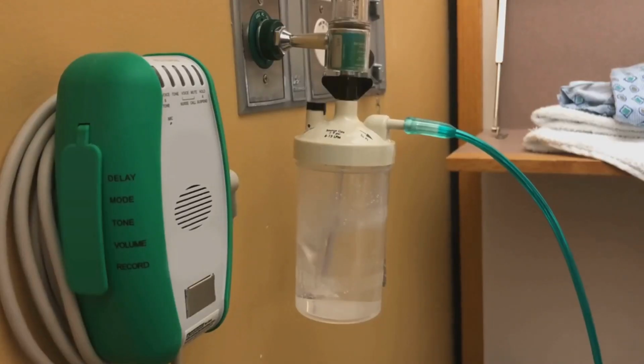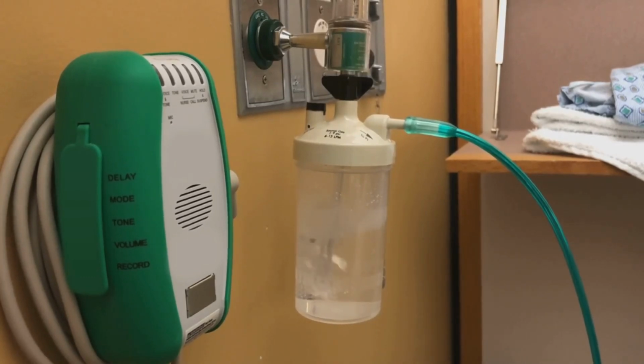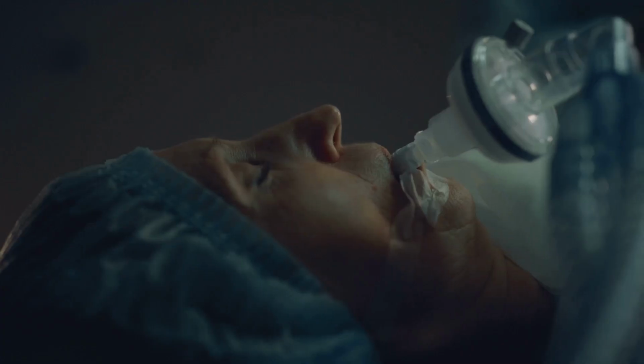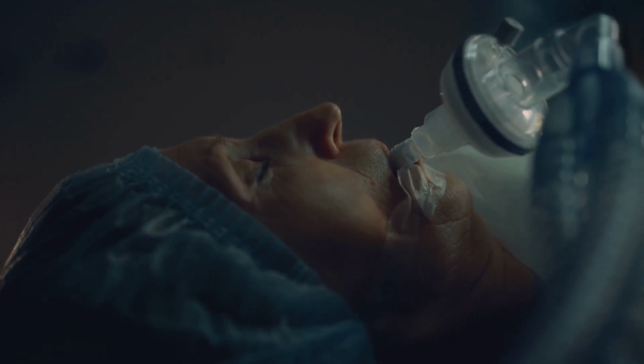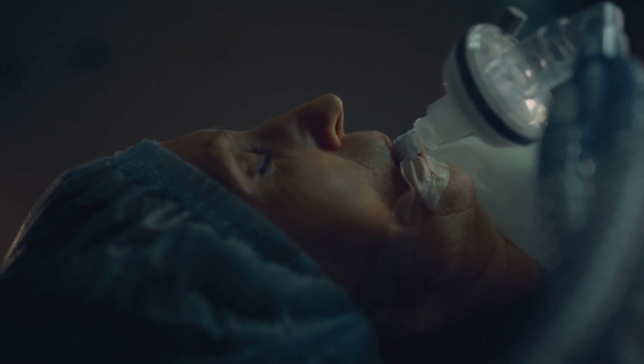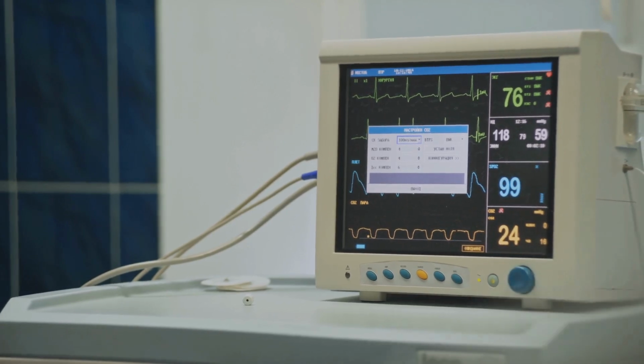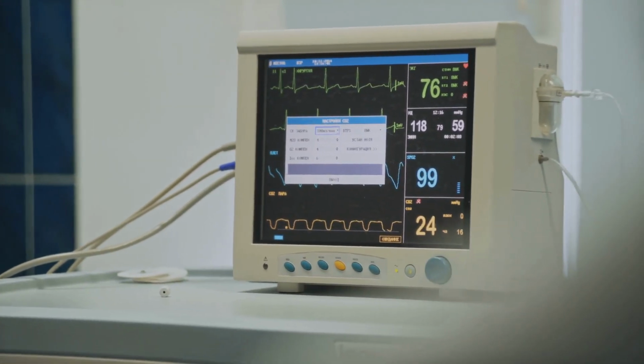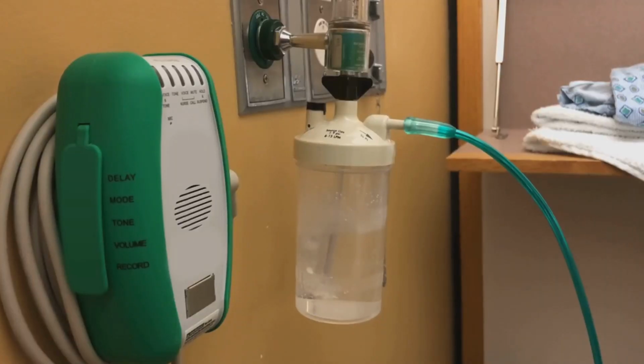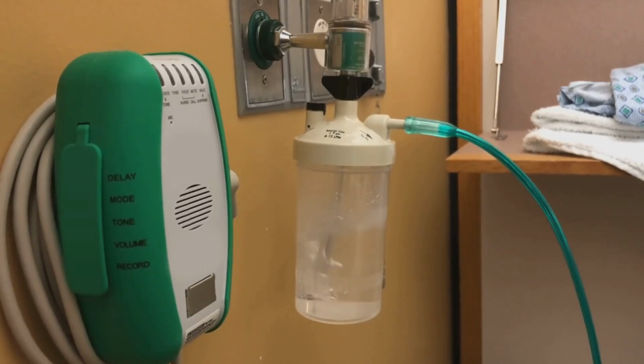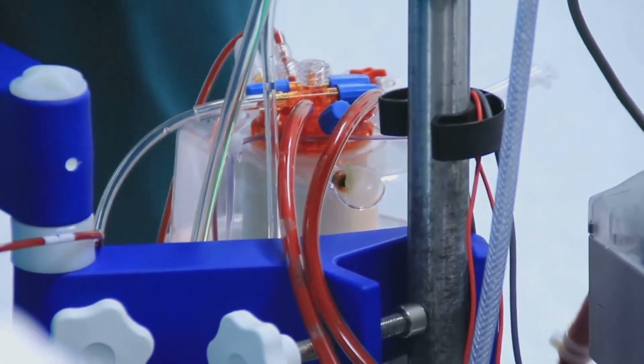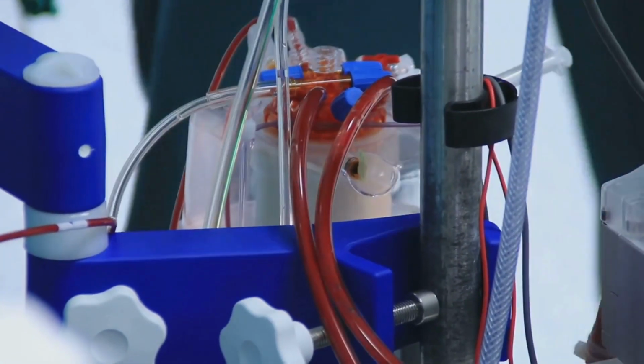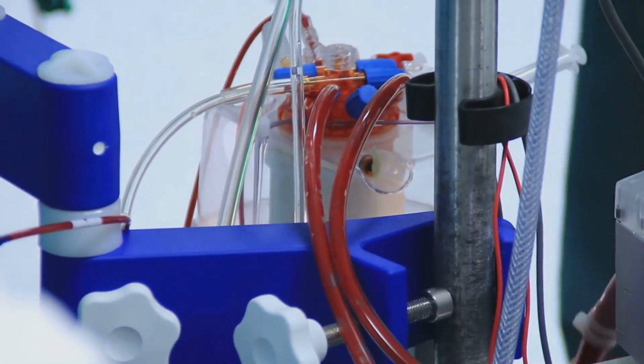The breathing system, on the other hand, is the conduit that delivers the anesthetic gases and oxygen from the machine to the patient. It also removes carbon dioxide that the patient exhales. The main parts of the breathing system are the breathing circuit, the carbon dioxide absorber, and the adjustable pressure limiting valve. The breathing circuit is like a two-lane highway. One lane carries fresh gas from the machine to the patient, while the other carries exhaled gas back to the machine. The carbon dioxide absorber then removes carbon dioxide from this exhaled gas before it's recirculated.